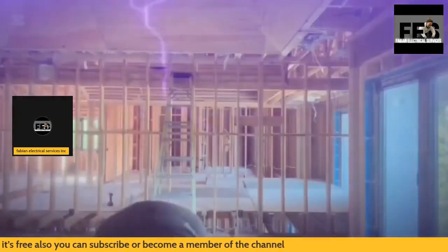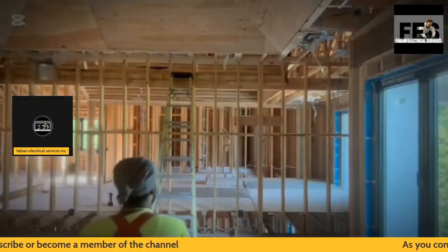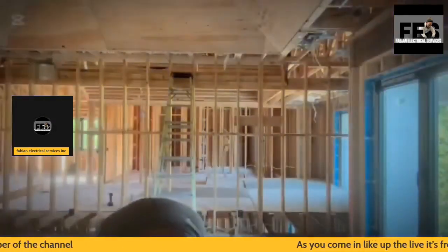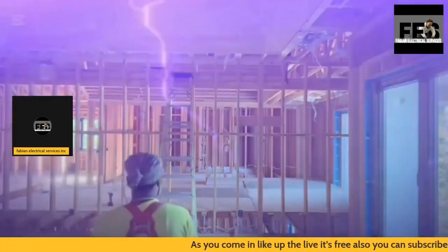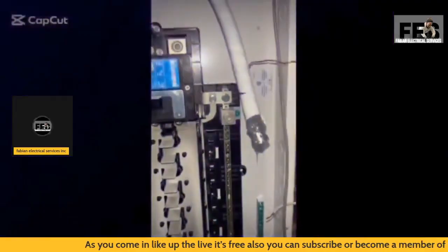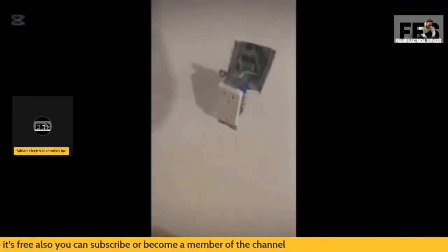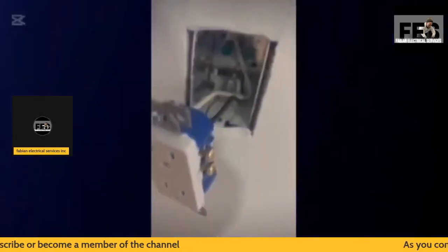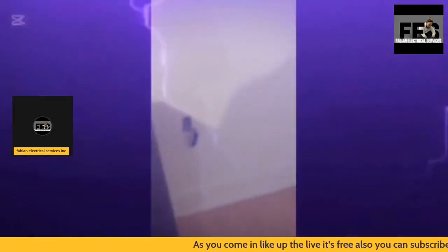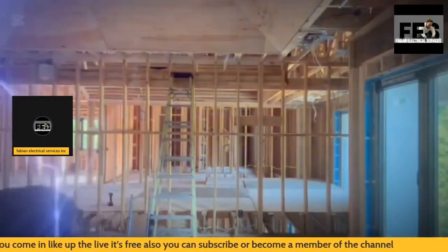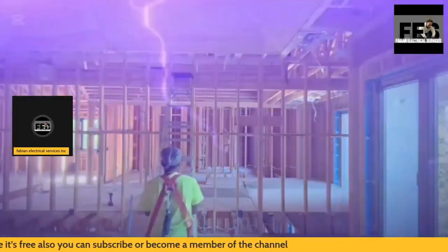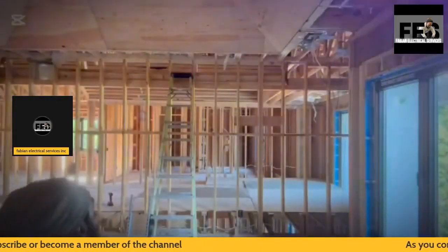And tonight we're going to be going through some code: breaker sizing, grounding and bonding, Canadian Electrical Code. We're going to be working off of the OESC 2024, and we're going to also get into Section 26-700, Section 30, and we're going to talk about sub panels and neutral installations. For now, I'm going to go into Section 14-606, which is a panel board location rule. So we're going to take a look at that rule.